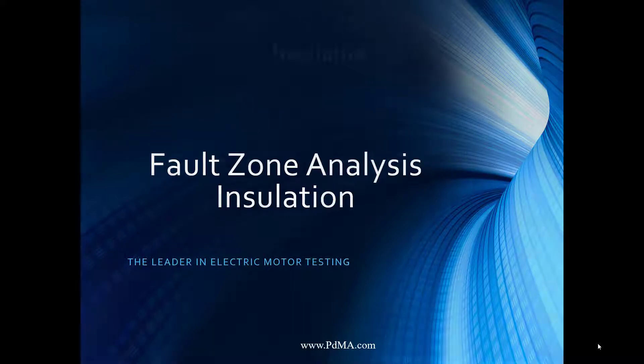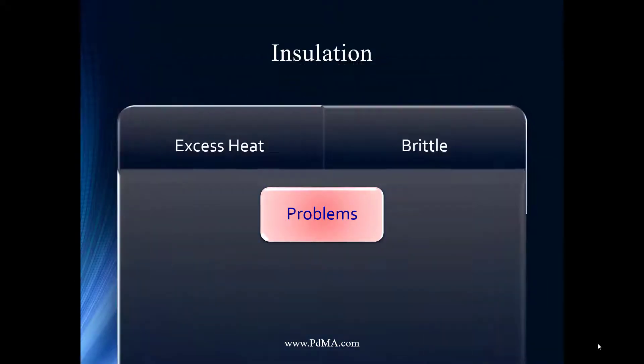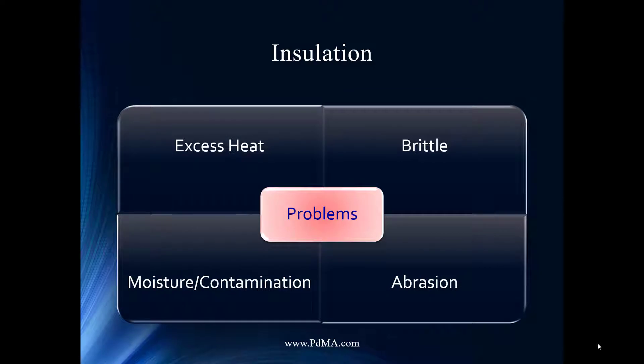Some of the problems we see with insulation include excess heat, brittleness, moisture, and abrasion. Noah: I always like to start with heat. Heat is considered the number one killer of a motor, and it really falls on the insulation as the final fault mode. We've got to maintain heat within the motor design. That heating, through expansion and similar effects, will create embrittlement issues over time.